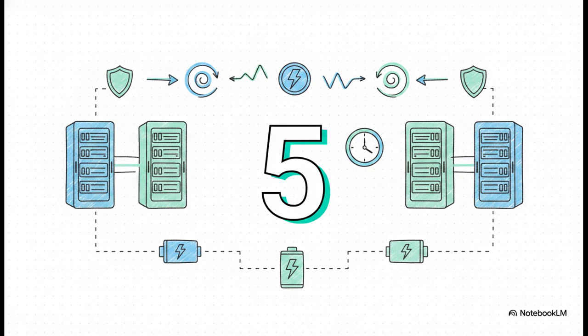5. That is the number of minutes of ride-through a rack-level BBU might typically provide. Now, 5 minutes isn't meant to run a data center through a massive blackout. It's a control surface. Just 5 minutes of local buffering allows a massive AI rack to gracefully hold its load while it confirms a second power source is completely healthy.